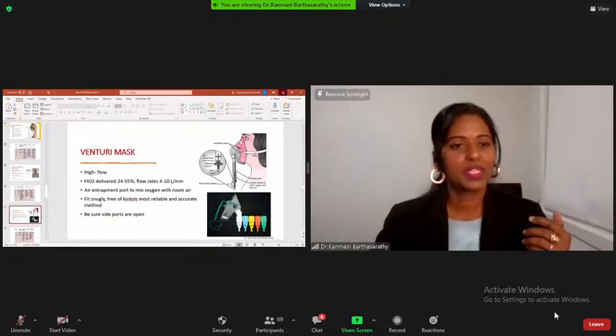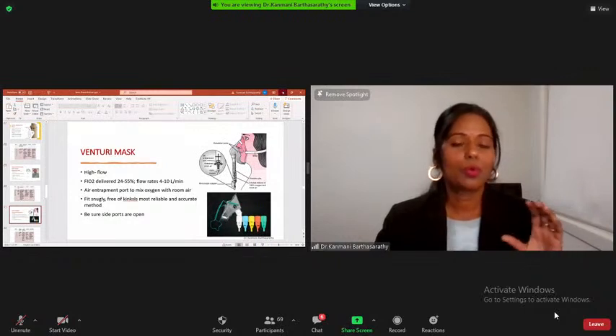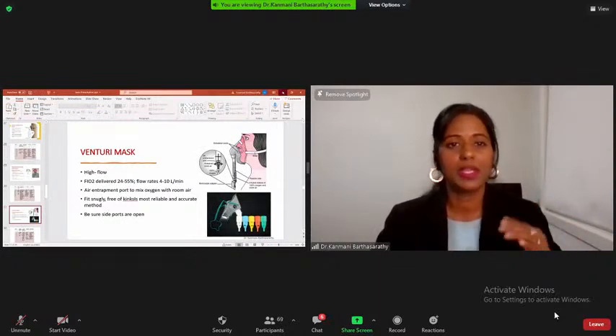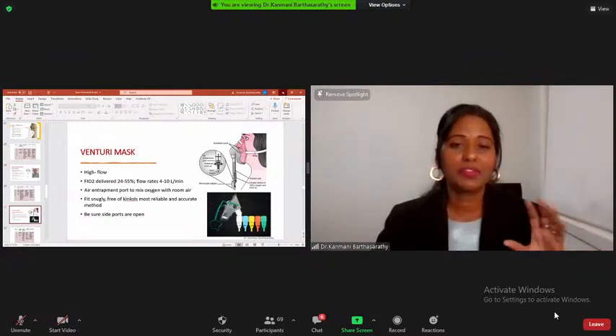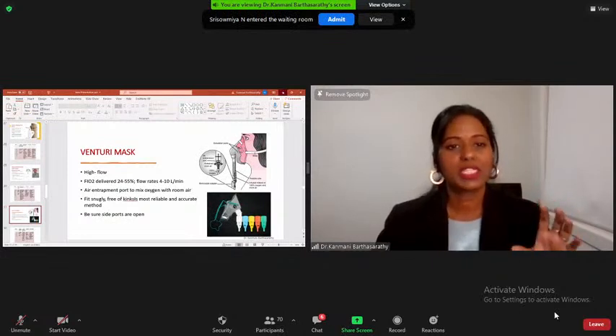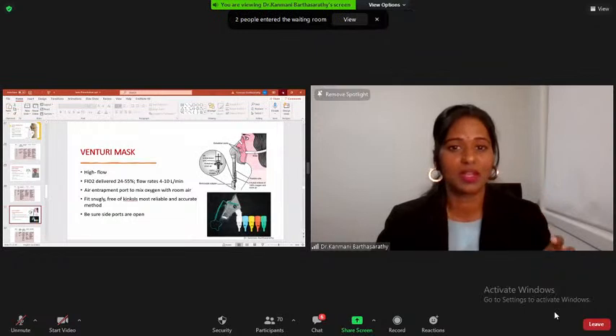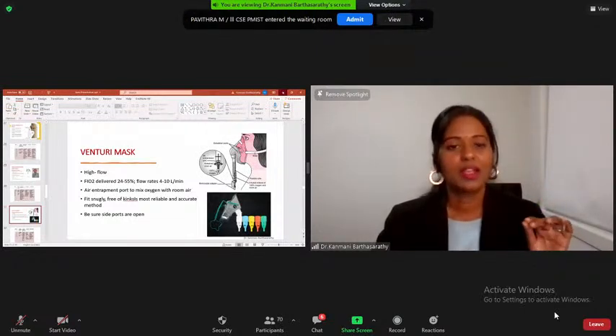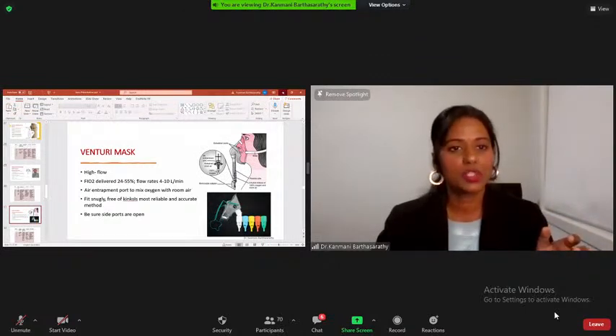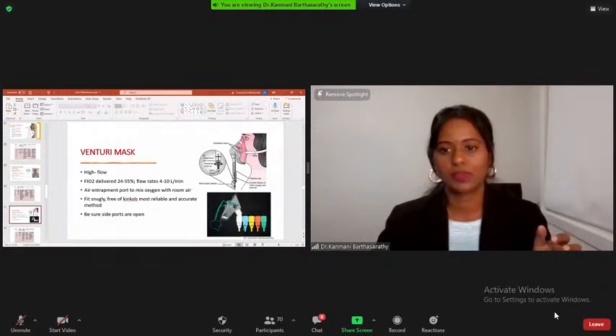Venturi mask. This is also called a fixed performance mask. The aim is to deliver a constant oxygen concentration within and between breaths. The minimum oxygen flow is 4 to 10 liters per minute. With tachypnea, the oxygen flow should be increased by 50%. Increasing flow does not increase oxygen concentration, as it is a fixed dose device. It is a good device for patients with raised carbon dioxide. Different colors deliver different flow rates. The correct flow rate to use with each color is shown on the mask along with the percentage of oxygen delivered. So the various colors deliver different percentages of oxygen concentration.